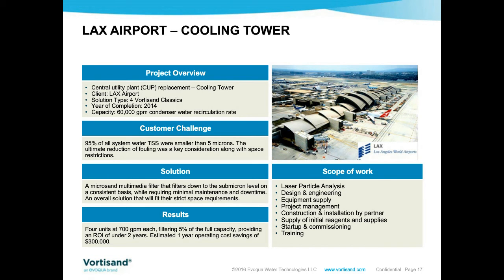Los Angeles Airport in 2014 required side stream filters for their cooling tower. So CROSSFLOW MICROSAND filters were supplied as a side stream filter, filtering about 5% of the loop flow. Laser particle counts are used to measure and count the number of particles in different micron size ranges. Laser particle counts here showed that 95% of the particles were smaller than 5 microns, which is what we expect from a cooling tower application with airborne particles and scaling and very small iron particles.